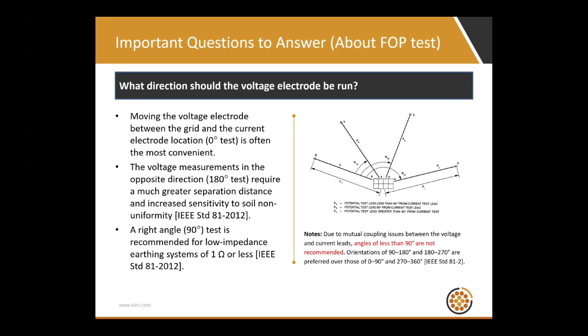the reasons for that. Some important recommendations here: if you can't measure at exactly 90 degrees, then it's better that you measure at an angle greater than 90 but less than 180 degrees, rather than between 0 and 90 degrees. Of course, these recommendations are ideal in an ideal world. If you could run your voltage and current leads in any direction you wanted, you would set up an ideal 90-degree test. But in practical terms, it doesn't often work out like that.